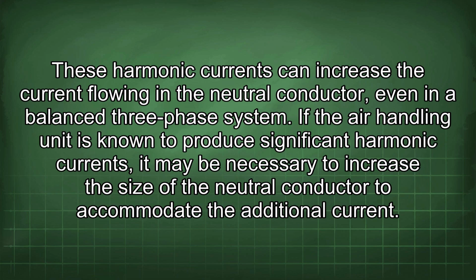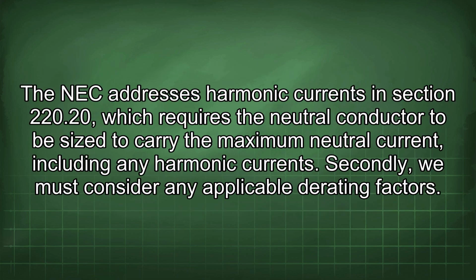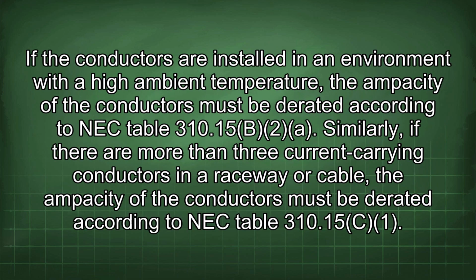If the air handling unit is known to produce significant harmonic currents, it may be necessary to increase the size of the neutral conductor to accommodate the additional current. The NEC addresses harmonic currents in section 220.20, which requires the neutral conductor to be sized to carry the maximum neutral current, including any harmonic currents. Secondly, we must consider any applicable derating factors. If the conductors are installed in an environment with a high ambient temperature, the ampacity of the conductors must be derated according to NEC Table 310.15(B).